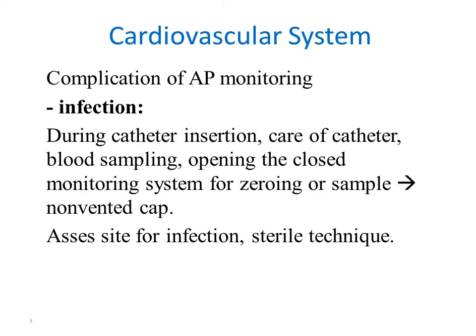Complication for arterial pressure monitoring: infection during catheter insertion. Care should be taken for the catheter during the blood sampling, opening the closed monitoring system for zeroing or sampling. All of these should be taken in consideration to avoid any infection, and taking care for the site of insertion using sterile technique to avoid any infection.